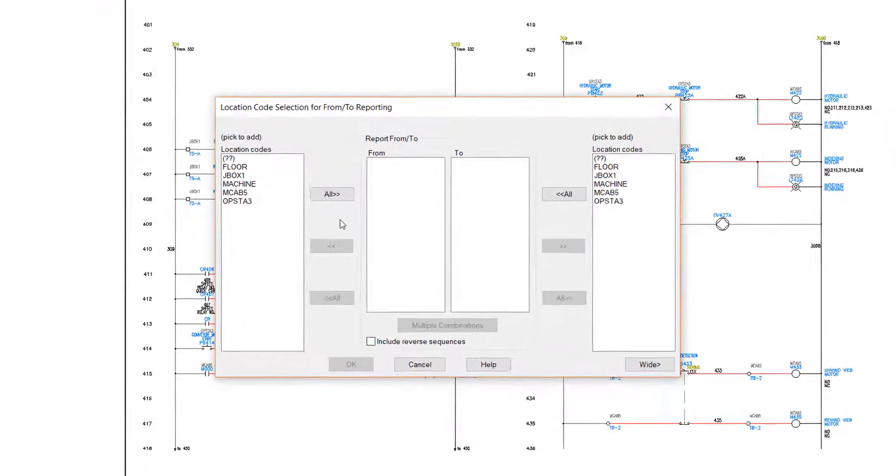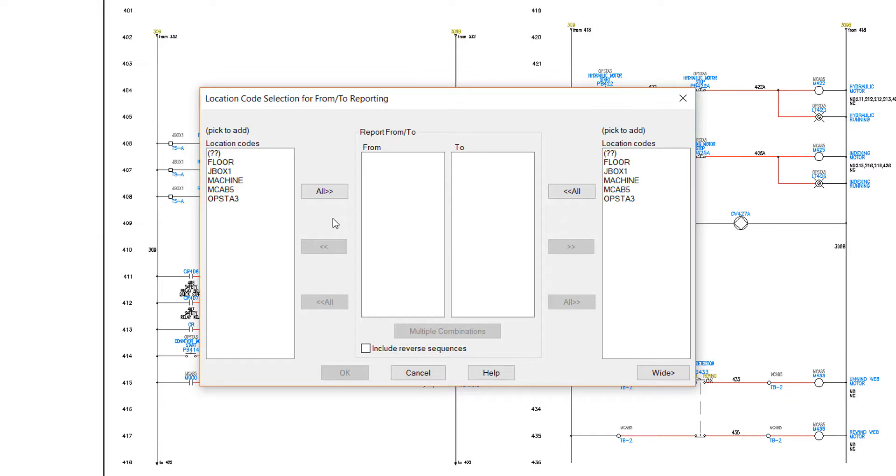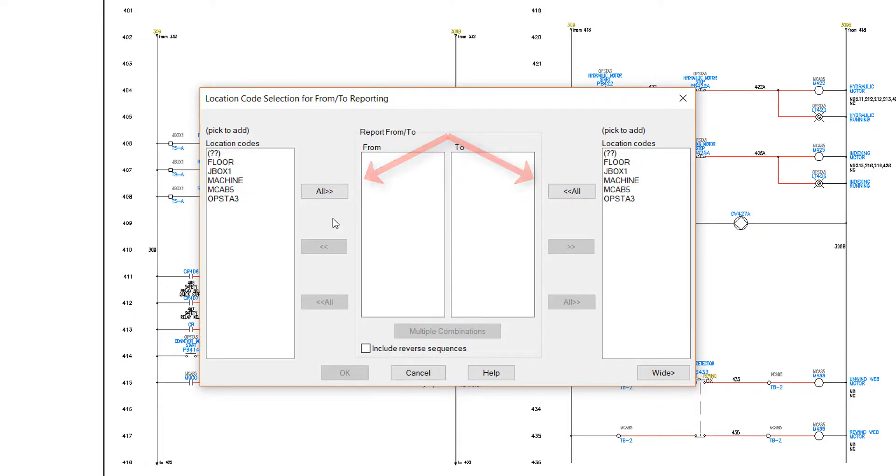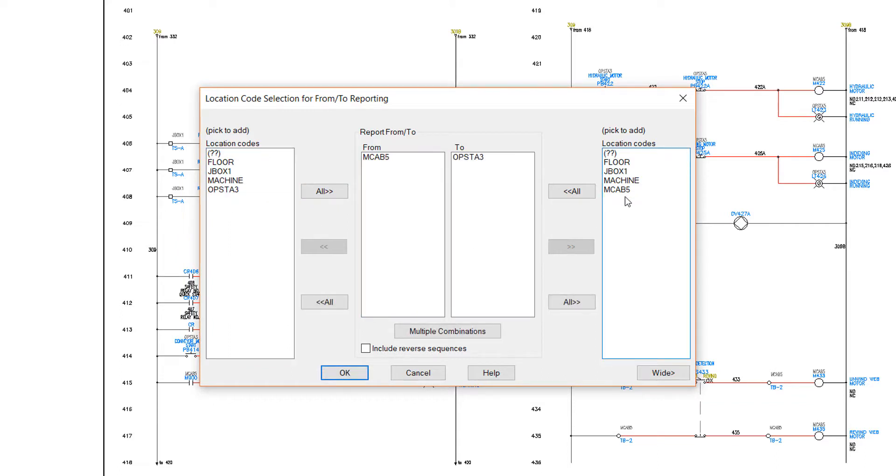In the old days of manual schematic design, one of my least favorite tasks was the Conduit Run Report. This is where I needed to list all of the wires that run from one location to another through a connecting conduit. Printed drawings and highlighters were my most important tools. To display all wires in the project, I can choose all for both the From and To locations. But to solve the conduit run challenge, I will use a slightly different option. I will select only MCAB 5 for the From display and only Operator Station 3 for the To display.